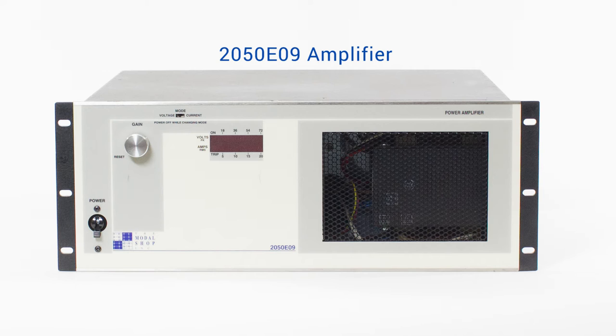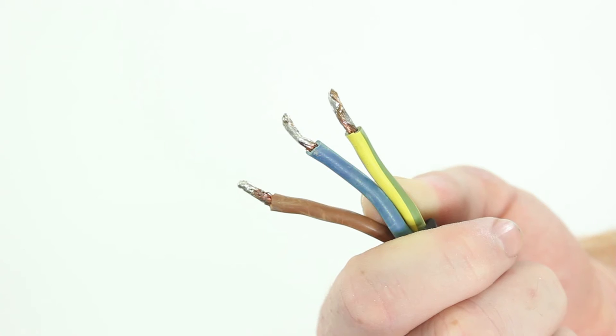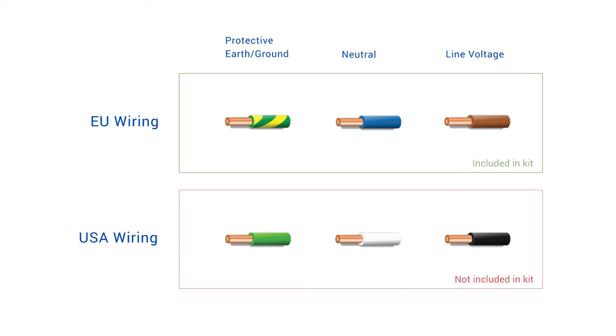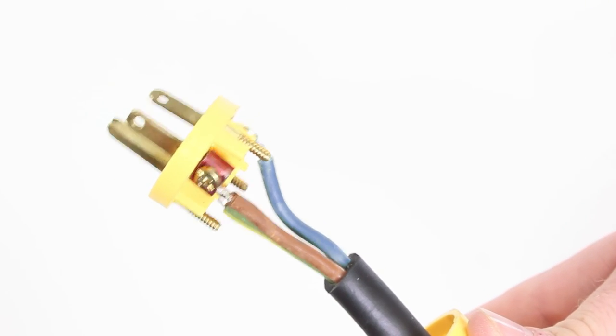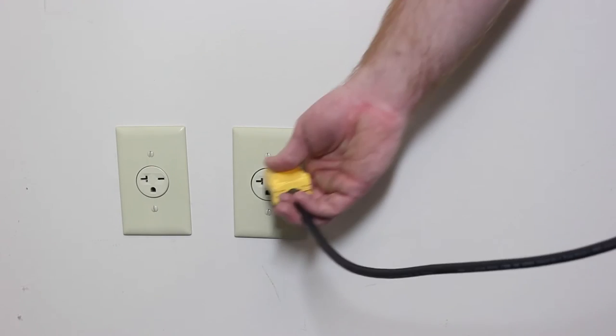First, we will need to provide power to the amplifier. The standard power configuration for the 2050E09 amplifier is 220-volt AC power. A three-conductor power cord using the EU wiring convention of striped green-yellow protective ground, blue neutral, and brown line voltage is provided and pre-installed on the amplifier. For reference, U.S. wiring convention is green protective ground, white neutral, and black line voltage. Because of the number of different 220-volt AC plug options and potential variations in building wiring, it is the end user's responsibility to provide and install the appropriate plug onto the cable and confirm the power is correct.